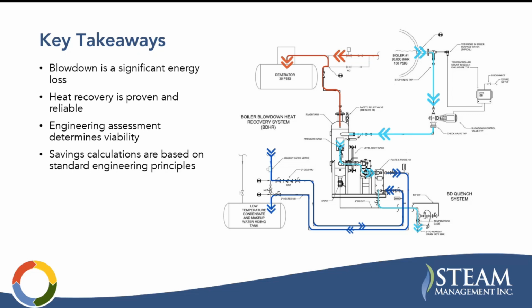That is a great question, and that's funny that you say that. Actually, this P&ID right here is from a project where they had manual blowdown, and this was a two-part project. We recommended a digitally controlled modulating blowdown valve. One aspect of the savings was that they would now be controlling to a conductivity reading and modulating that flow, minimizing the amount of blowdown lost. So they're just rejecting exactly the amount that they need to keep the TDS levels appropriate. So that's part of the savings. And then they still do have a blowdown requirement, and it was still enough to warrant a blowdown heat recovery system. So that's where I pulled this from, one of our projects.